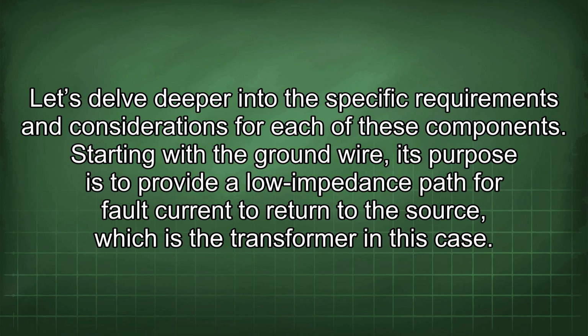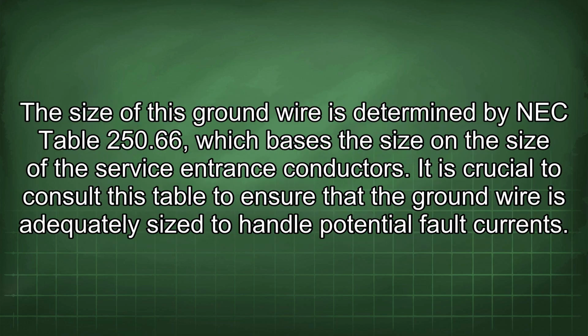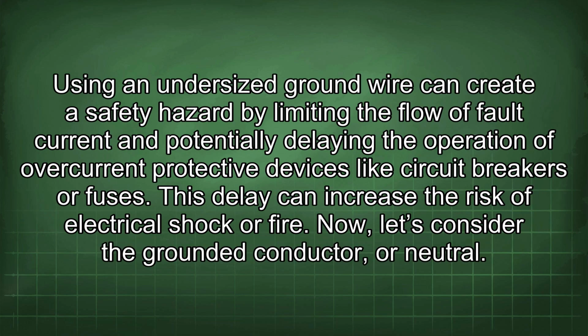Starting with the ground wire, its purpose is to provide a low impedance path for fault current to return to the source, which is the transformer in this case. The size of this ground wire is determined by NEC Table 250.66, which bases the size on the size of the service entrance conductors. It is crucial to consult this table to ensure that the ground wire is adequately sized to handle potential fault currents. Using an undersized ground wire can create a safety hazard by limiting the flow of fault current and potentially delaying the operation of overcurrent protective devices like circuit breakers or fuses. This delay can increase the risk of electrical shock or fire.